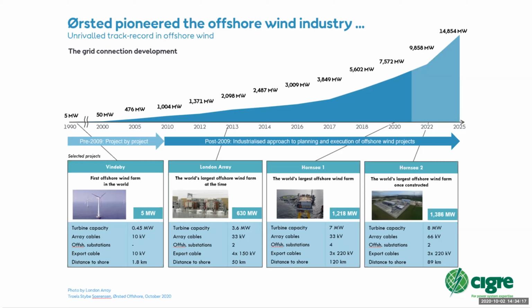The London Array project, on the other hand, in 2012 I think, was already 630 megawatt, connecting the wind turbines at 33 kilovolts and using two 150 kilovolt offshore substations connecting to land with 4 parallel 50 kilometer long export cables to a large dedicated onshore substation.